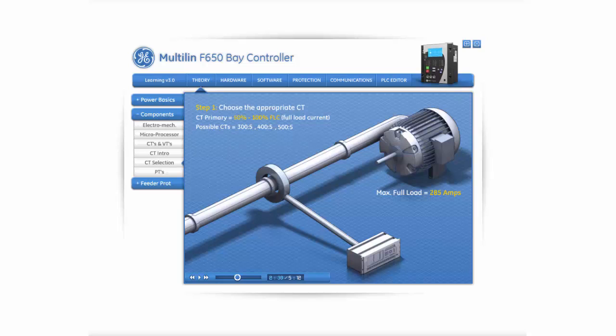The reason for this is the higher the CT ratio is over the full load current, the less sensitive that CT will be. Since accuracy is always imperative, we will select a CT with a 300 to 5 amp conversion, where the primary rating is 300 and closest to the 100% primary rating. The next step is to ensure this CT doesn't saturate under worst-case fault conditions. If it does, a higher ratio CT, such as the 400 to 5 CT, may need to be chosen.